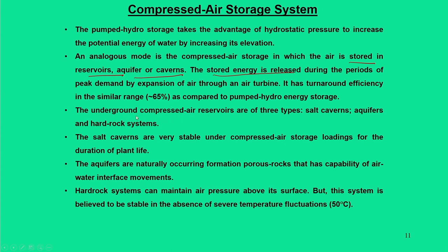Compressed air storage systems can be of three types: salt caverns, aquifers, or hard rock systems. Salt caverns are more stable compressed air storage systems due to their loading stability for the entire plant life duration. Aquifers are naturally occurring formations of porous rocks with capability for air-water interface movements, so that pressure difference can be utilized as storage. Hard rock systems maintain air pressure above their surface, but the main issue is instability under large temperature fluctuations. Our main focus will be on salt cavern systems, which are more stable and simpler in operation.